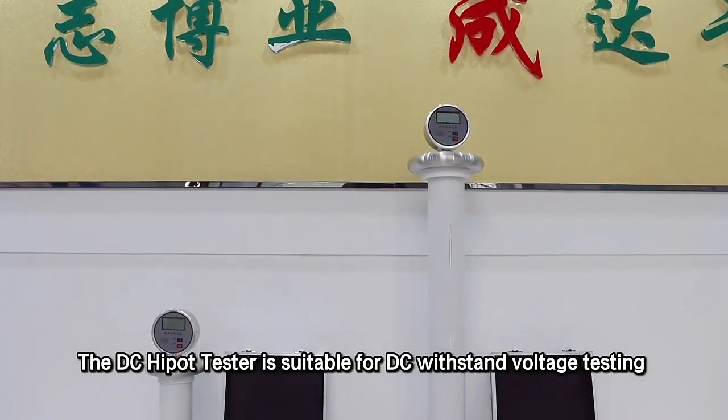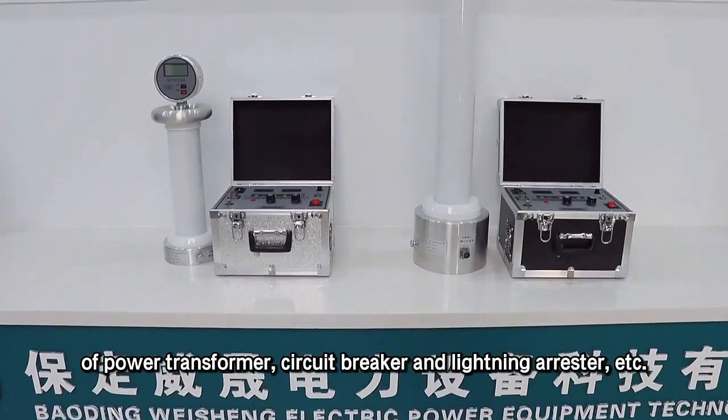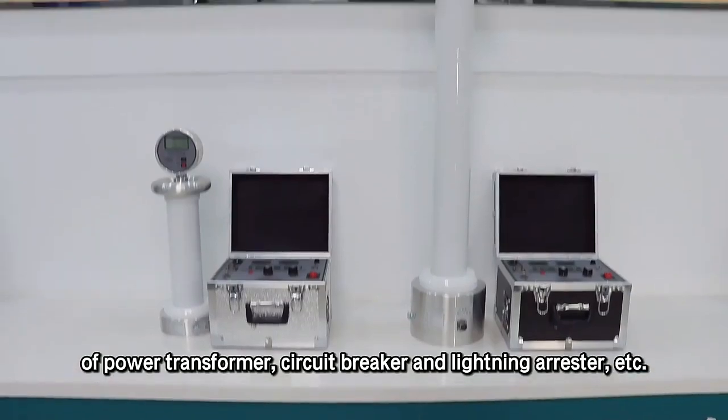The DC hipot tester is suitable for DC withstand voltage testing and DC leakage current testing of power transformers, circuit breakers, lightning arrestors, etc.